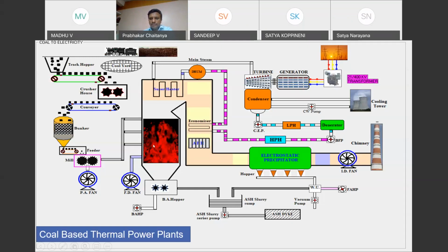For ensuring the airflow, we need to have a draft. So air draft: this is the forced draft fan, and this is the induced draft fan. By means of these two fans, air will flow continuously into the boiler. Then there is an important component called the electrostatic precipitator. Once coal is burned, there will be ash particles in the flue gas. We should not let the particulate matter enter into the atmosphere. The electrostatic precipitator, because of its high voltage of around 70 to 80 kV, will remove the particulate matter from the flue gas stream.